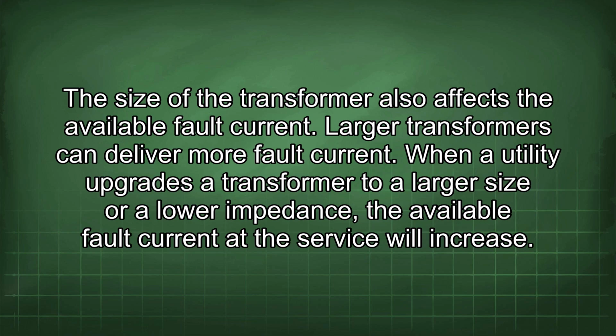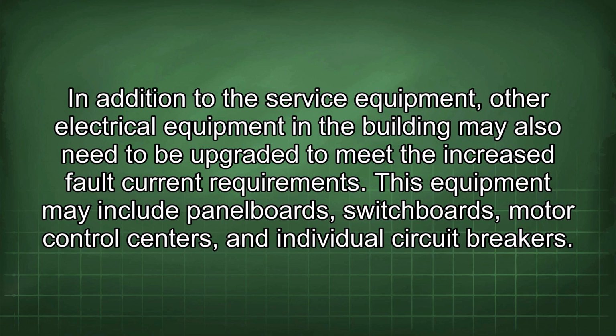When a utility upgrades a transformer to a larger size or a lower impedance, the available fault current at the service will increase. In addition to the service equipment, other electrical equipment in the building may also need to be upgraded to meet the increased fault current requirements. This equipment may include panel boards, switchboards, motor control centers, and individual circuit breakers.